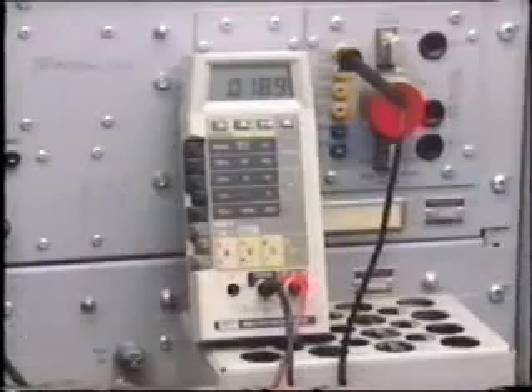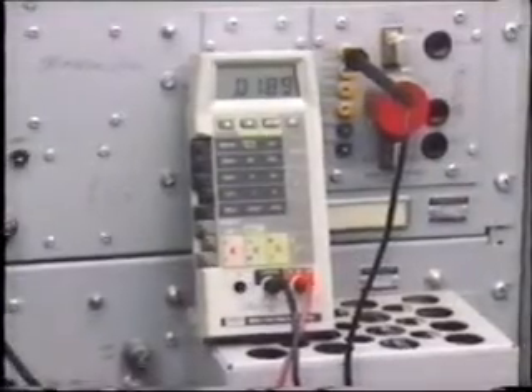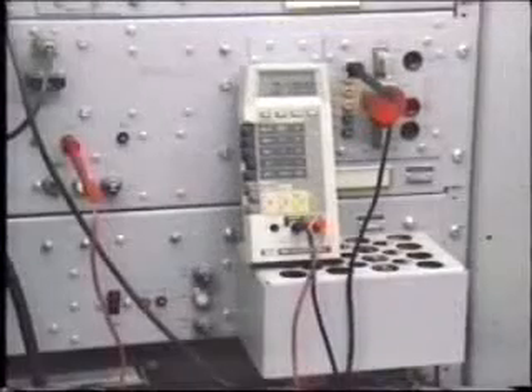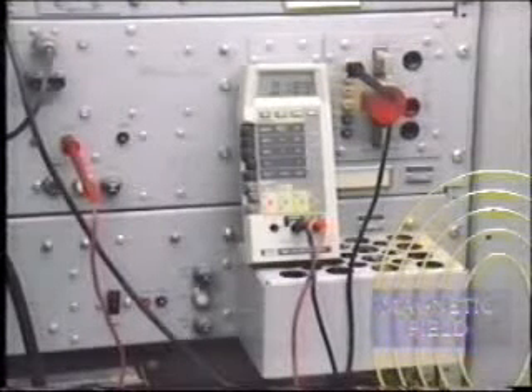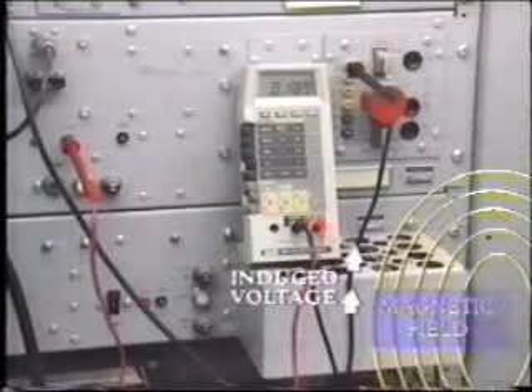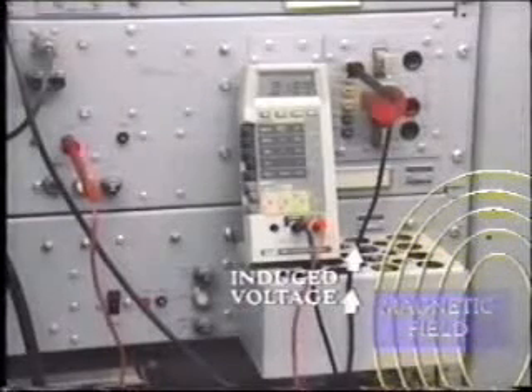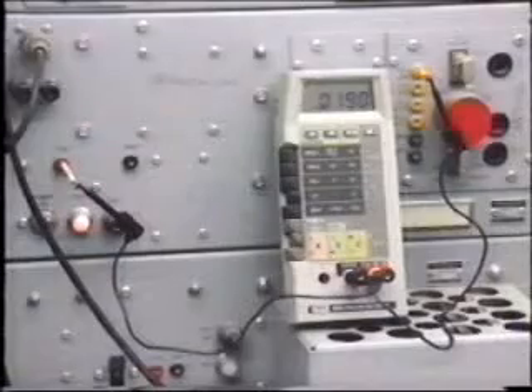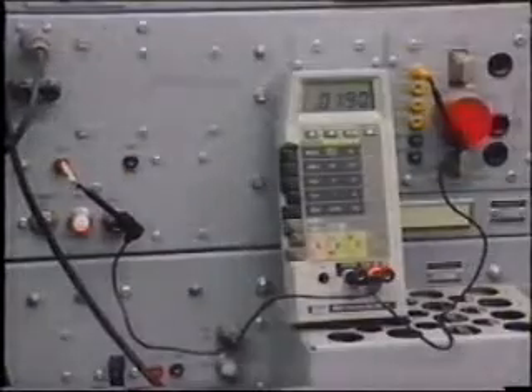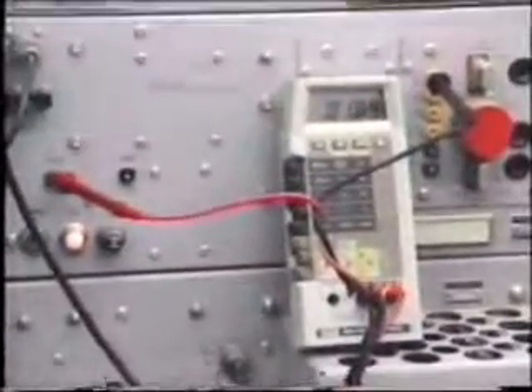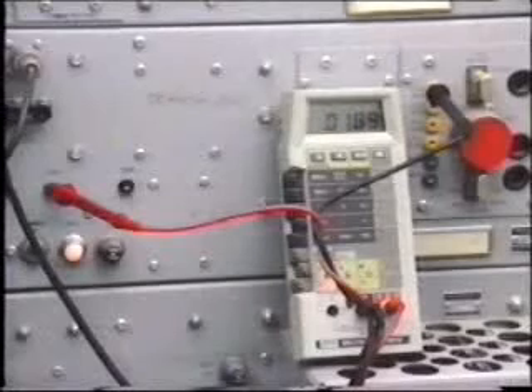Measurement errors are very likely to occur when using digital instruments in close proximity to electrical and magnetic fields. Here, we are trying to measure a small voltage across a high-resistance circuit which is located in a substation. The probability is that the nearby magnetic fields will induce a current into the meter test leads, and this in turn will produce a voltage which is superimposed upon the measured signal. Clearly, one way to reduce this error is to keep the test leads as short as possible. If you do have to use long leads, then twist them together throughout the length. In this manner, the interfering flux should be counteracted.